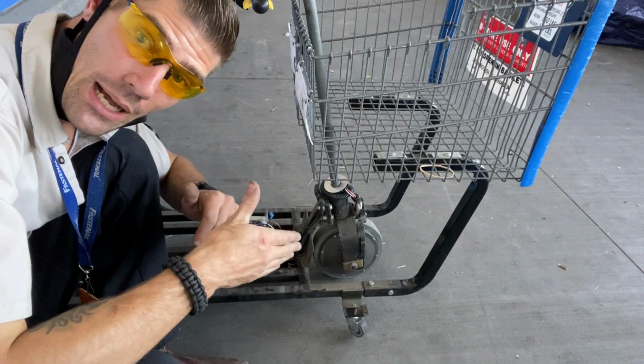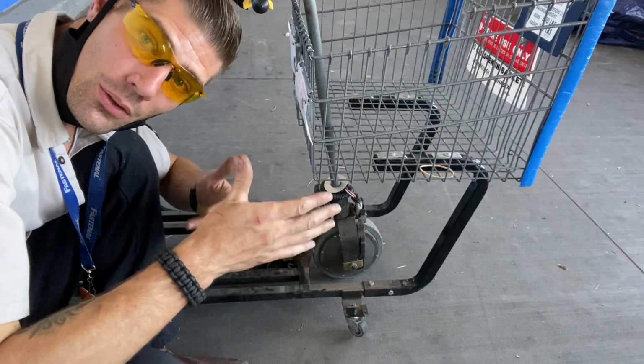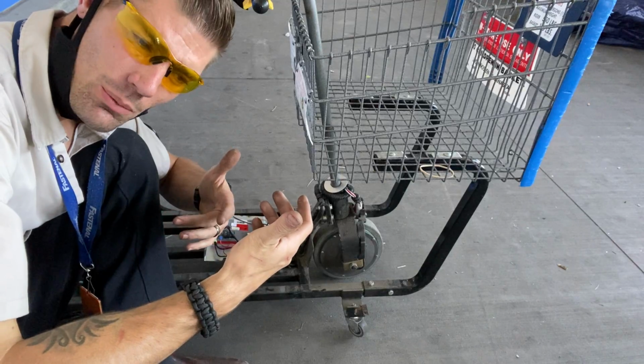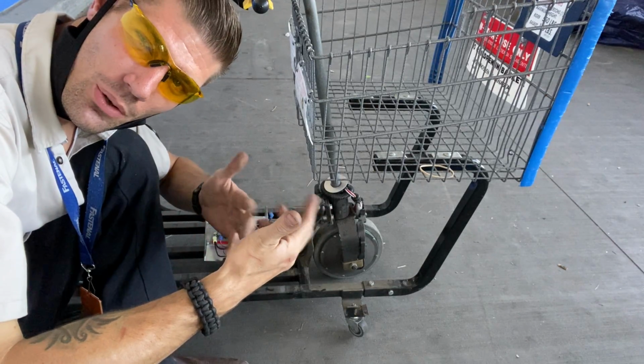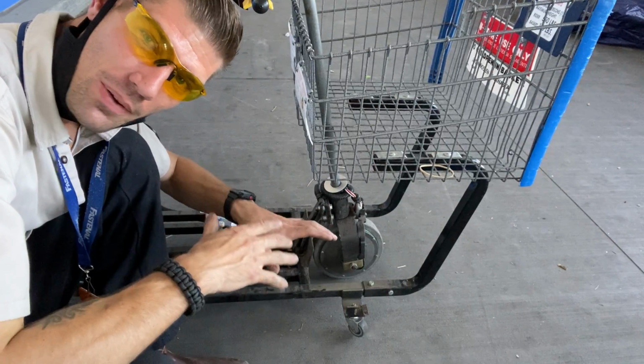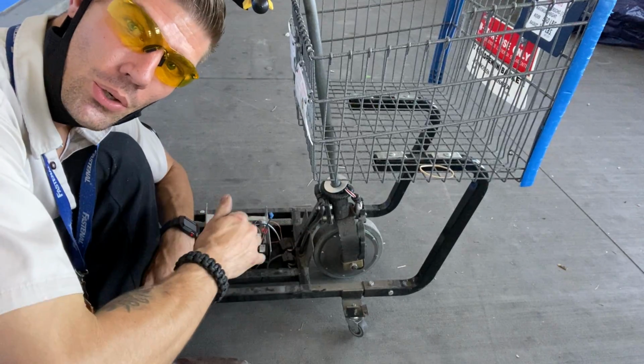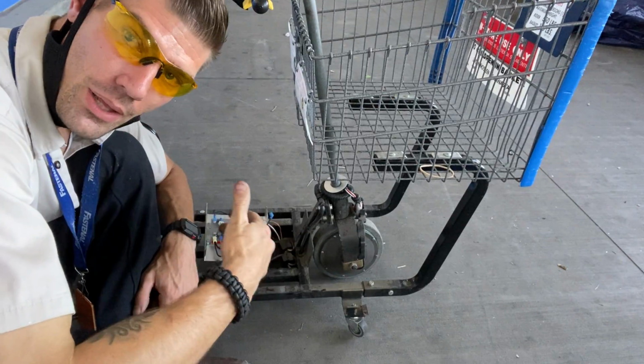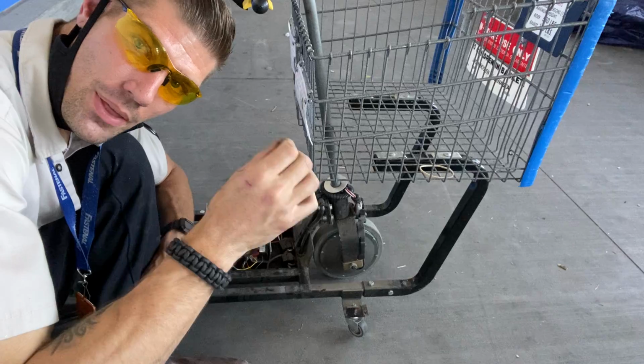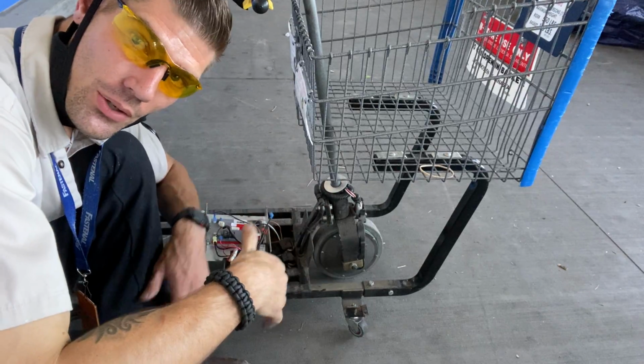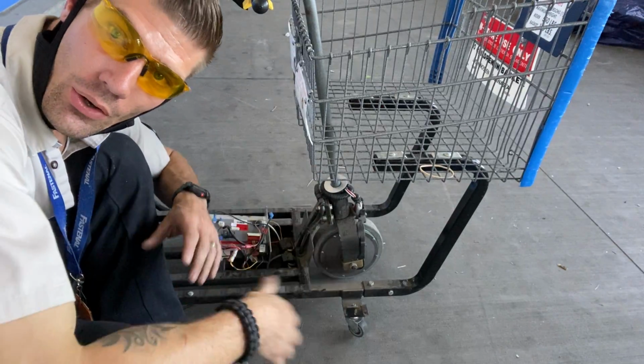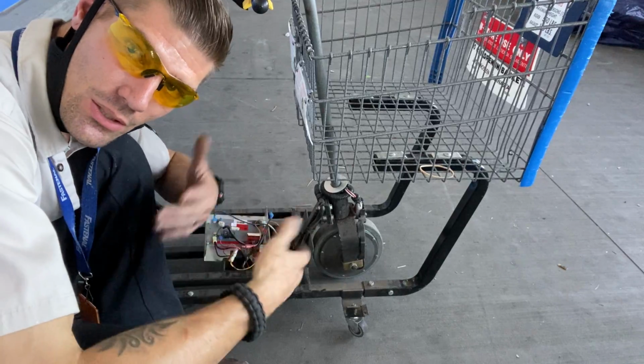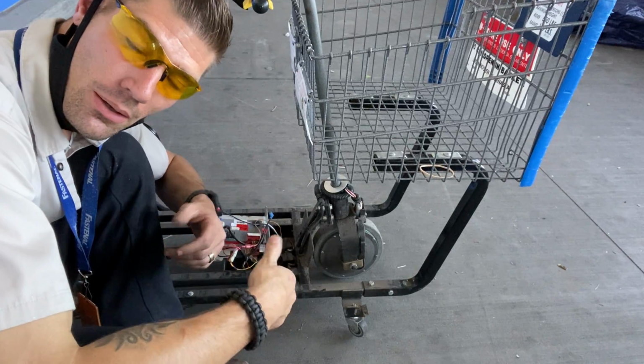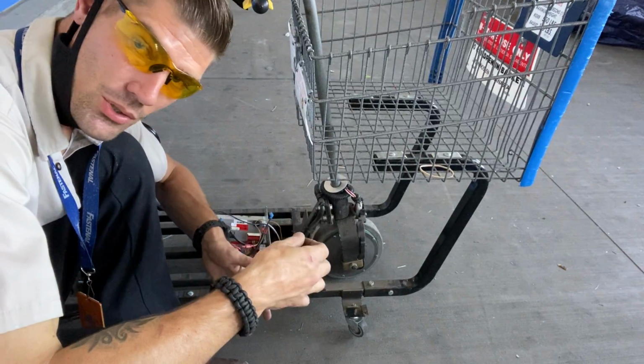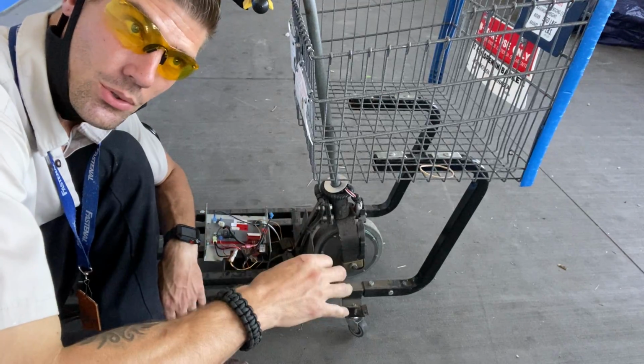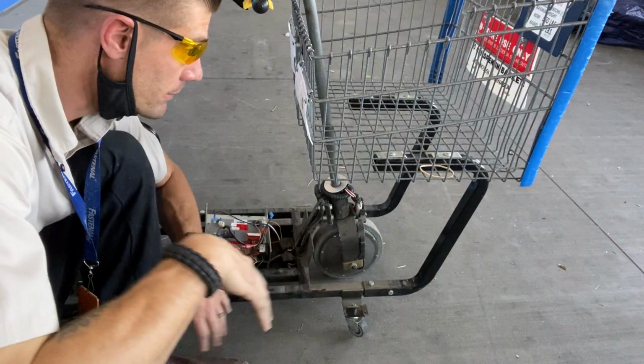I know I've got voltage out to it and it's not running - your motor is bad. It's about $400 to $600 for a motor. That's why it's important to justify your purchases. Troubleshooting, critical thinking, problem solving, attention to detail - those little things add up. $500 here, $100 here, over weeks and months, that starts adding up to a few thousand dollars. So let's justify our purchases with good troubleshooting, technical skills. That's what I'm trying to do here today.